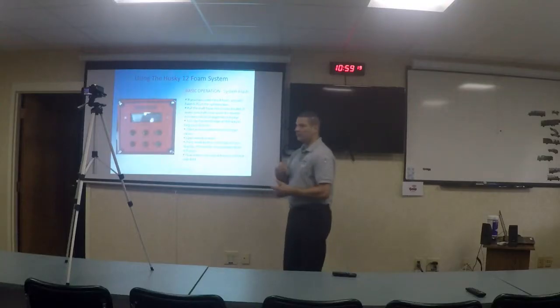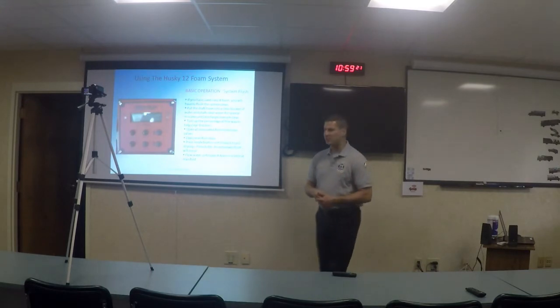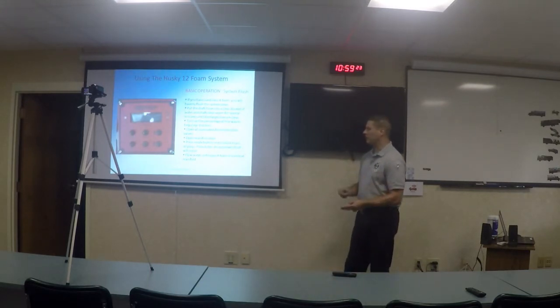You're going to go through those displays until whatever shows up on the screen matches what you're going to use. I don't think there's a mode for alcohol resistant AFFF, so you would just use Class B for that. Does that make sense? So if you do use something different from what's in the tank, you have to go through this flushing process. There are two ways that the flush is going to occur.